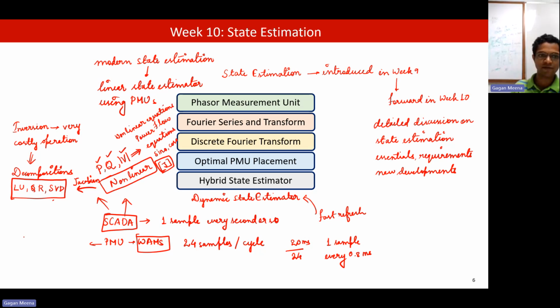That was for SCADA. Now with PMUs, we have current and voltage phasors, so both magnitude and angle are available. That makes the state estimator linear. We have a linear state estimator here, and that is why it becomes very fast.